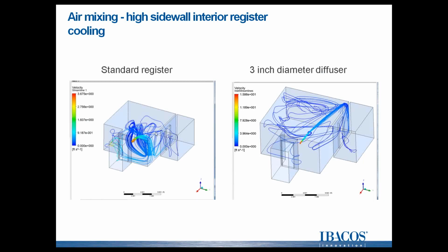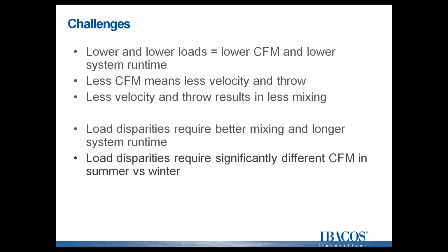And similar behavior is seen in the cooling mode, where again we have a little bit more stratification with the standard register. The air just kind of spills out, whereas with a little bit higher velocity, you actually mix that room better. And that's a strategy we'd like to suggest when it comes to lower and lower loads. But it's not all that easy, because you do still have to be aware of the occupied zone, and diffuser placement is crucial. You can't have these increased velocities in the occupied zone, or you might end up with complaints about drafts. So diffuser placement is also very critical if you're using these systems.